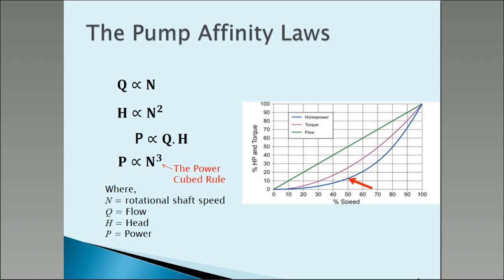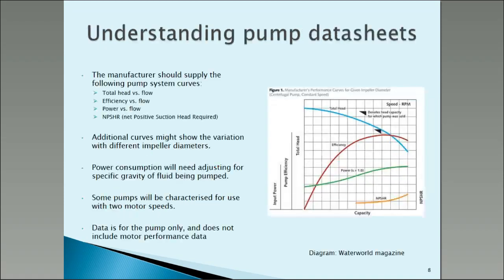What we do have to watch is what's happened to the pressure. The pressure obviously falls as the flow comes down. Now, if you're in a pumping system and you're not too bothered about the pressure, that's great. But if you did need the pressure — for example, you're pumping up a hill to a reservoir — then losing that head is bad news. So pump affinity laws are great, but if you've got a lot of static head to pump uphill, that's the problem.